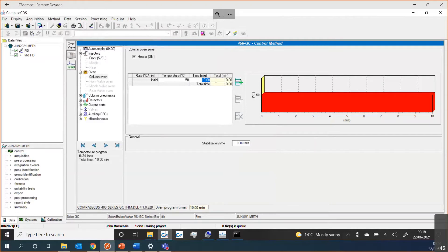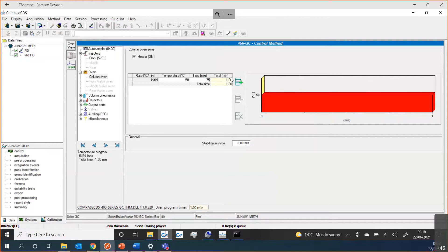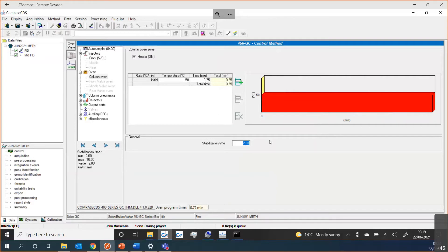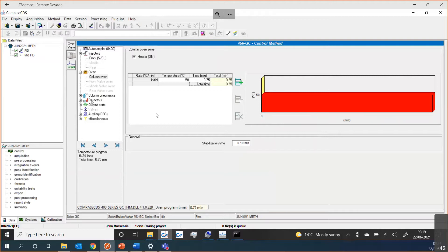I could check the various parameters for my method. We'll maybe just set that to a minute because if we're going to do a run, we don't want it to take too long. Maybe just 0.75, that'll be a bit quicker. I'll reduce my stabilization time. Normally for your GC, especially if you're doing temperature program runs, you would want your stabilization time to be a suitable amount of time for the oven to have cooled to the correct temperature and be at a good starting point for your analysis. I'll set this just to a low number because we want everything to work quite quickly.